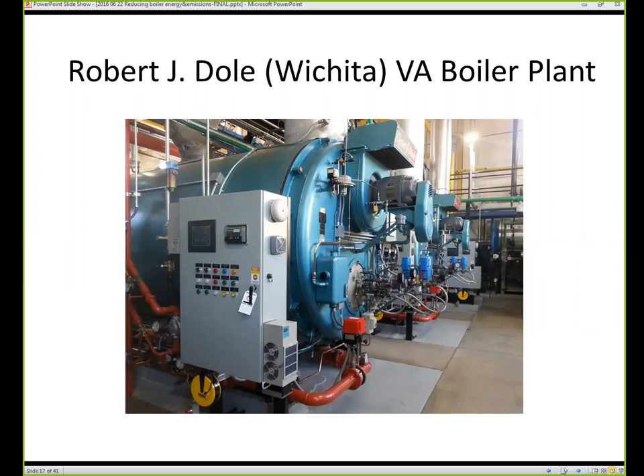It includes 6 community-based outreach clinics. The boiler plant serves a medical center comprised of a 41-bed hospital, 32-bed nursing facility, and 8-bed hospice care unit. I serve the VA as the boiler plant manager and have worked for the VA for more than 33 years in our plant. We have one 300-horsepower Cleaver-Brooks fire tube, 1966, 2 Cleaver-Brooks fire tube 350s, 1966, and the baby, a Johnson wetback, 1985. It's a 200. These boilers have never been retubed and run about 84% efficiency.